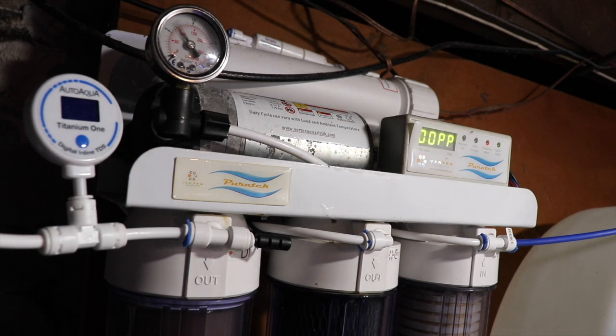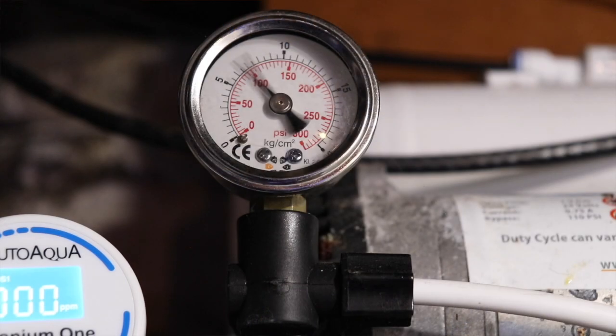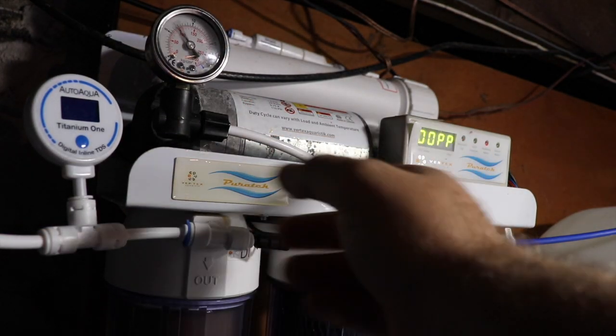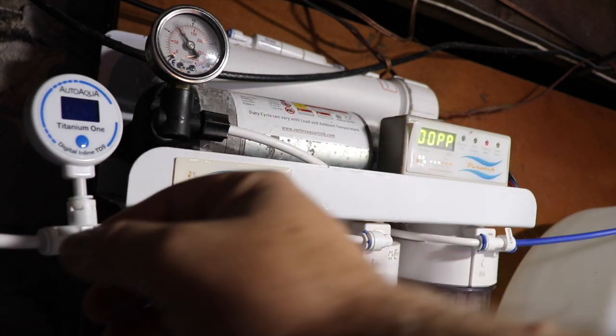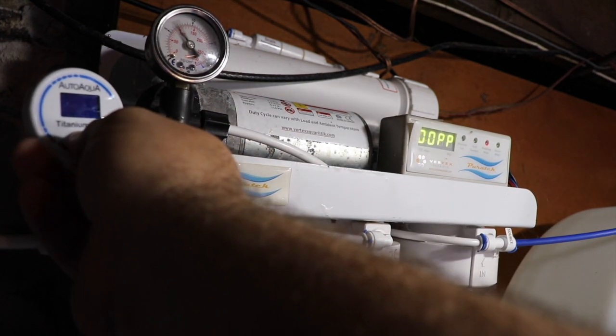So it's holding up pretty good. You can hear that ticking. I got the mic pointed back at me right now, but you can see there's a good amount of pressure right there, 100 PSI coming out of the RO membrane, or actually before it passes through the RO membrane.